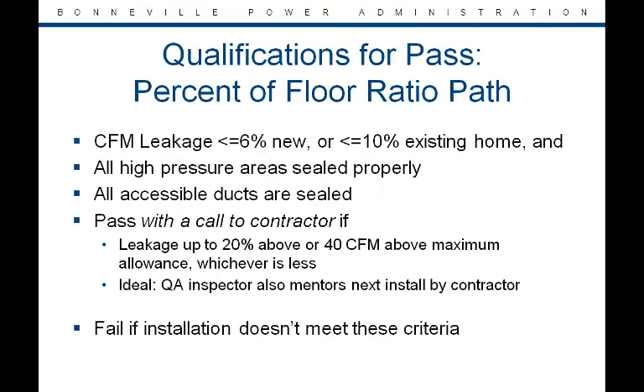If a duct system was PTCS certified based on the leakage as a percentage of the home's square footage, then that leakage must meet that standard. All duct sealing jobs must have all accessible ducts sealed, paying special attention to high-pressure areas.